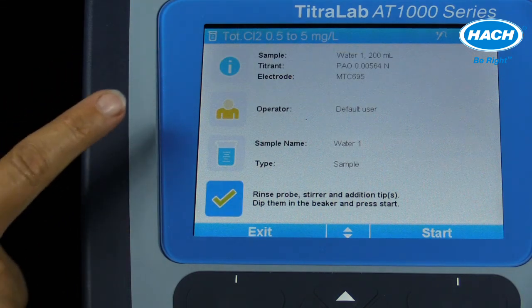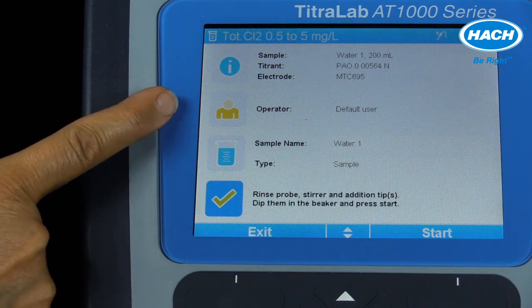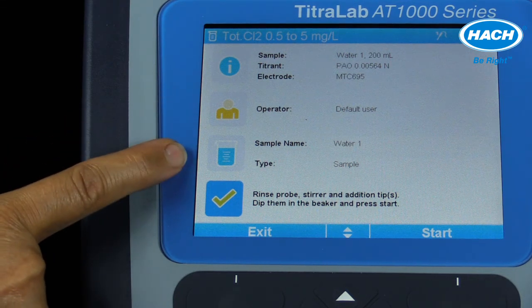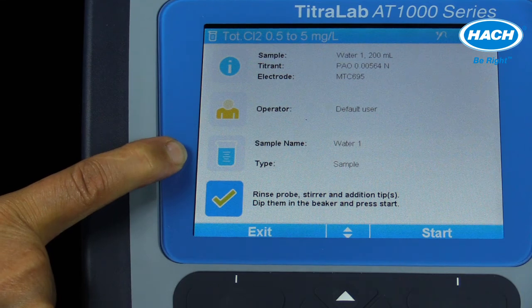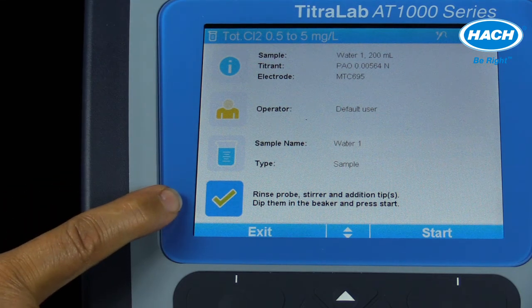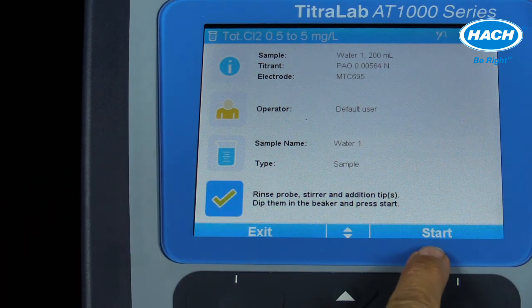Once the titrator has been set up with the titrant, reagents, syringe, electrode, sample, and application loaded, the titration is easy to perform by selecting Start. This easy operation is because the loaded application directs the titrator to dispense the titrant accurately, add necessary reagent, determine the inflection or endpoint, and calculate the result automatically. The results are then stored in the data log for easy transfer and traceability, all leading to improved result reproducibility, accuracy, and productivity.